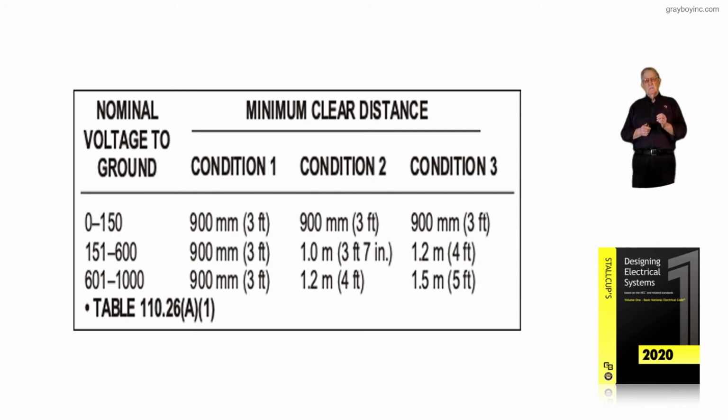So we were having problems with interpretations there, would not allow that overhang there, you'd have to be up at a greater height. So this is allowing it to be there under the conditions of 110.26(E)(2) with the exception being applied, and that's what our figure 5-10, say dot 2 or B, illustrates.